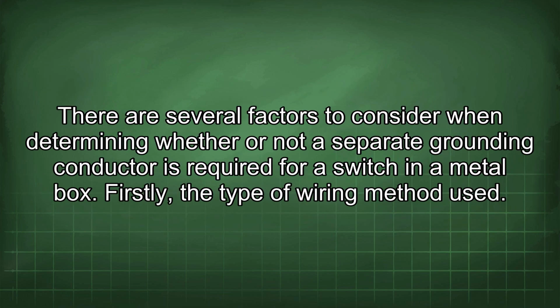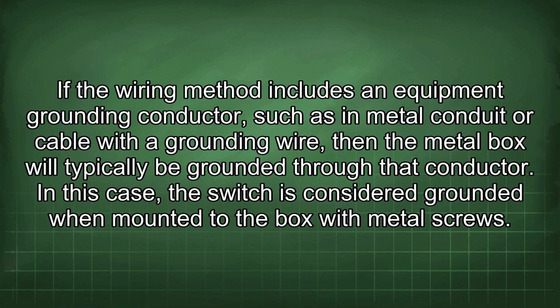There are several factors to consider when determining whether or not a separate grounding conductor is required for a switch in a metal box. Firstly, the type of wiring method used. If the wiring method includes an equipment grounding conductor, such as a metal conduit or cable with a grounding wire, then the metal box will typically be grounded through that conductor. In this case, the switch is considered grounded when mounted to the box with metal screws.